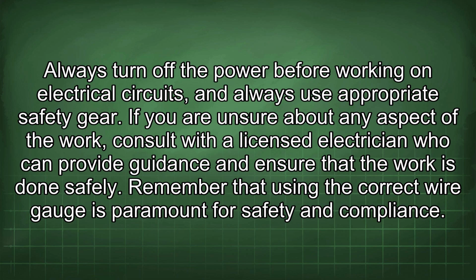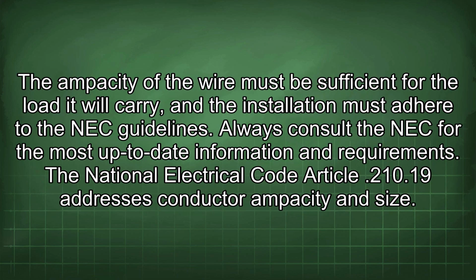Remember that using the correct wire gauge is paramount for safety and compliance. The ampacity of the wire must be sufficient for the load it will carry, and the installation must adhere to the NEC guidelines. Always consult the NEC for the most up-to-date information and requirements. The National Electrical Code Article 210.19 addresses conductor ampacity and size.